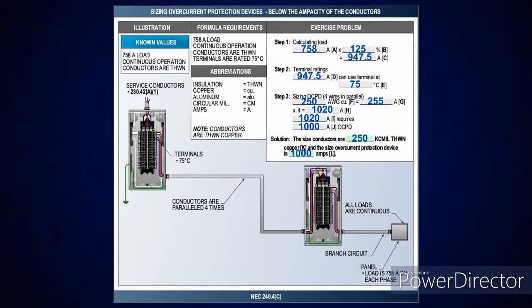Now, here's 240.4C, and on each phase here, I have 758 amps of continuous load. If it's continuous, naturally I take it at 125%. Now watch this. That gives me 947.5 amps. Now I'm saying we're going to parallel this 4 times. So I'm going to have to find something that is above that 947.5 amps. If you did this calculation, you should have come up with this: if you picked up your 250 kcmil, that's going to give you 255 amps. If I take the 255 amps times 4, that's going to give me 1,020.